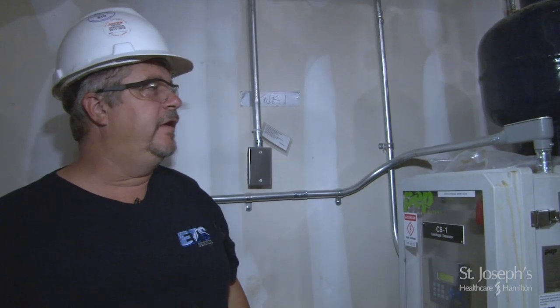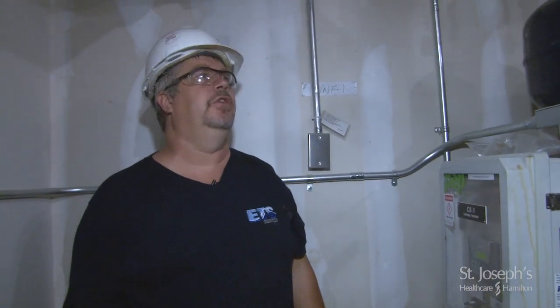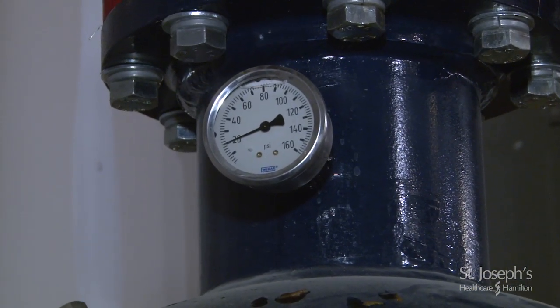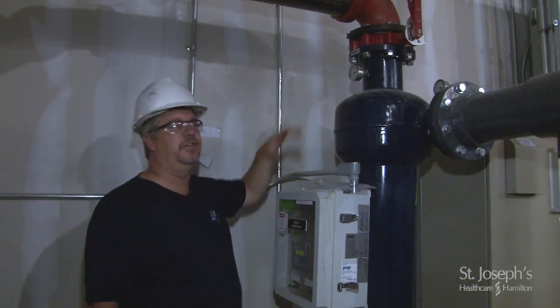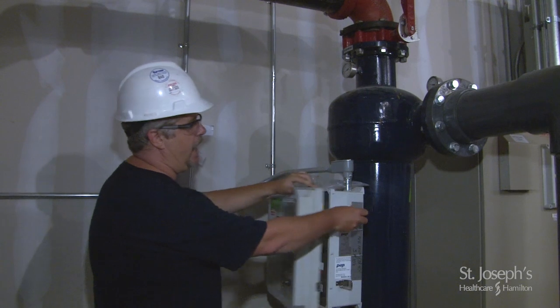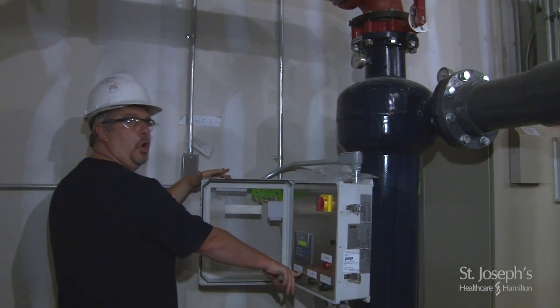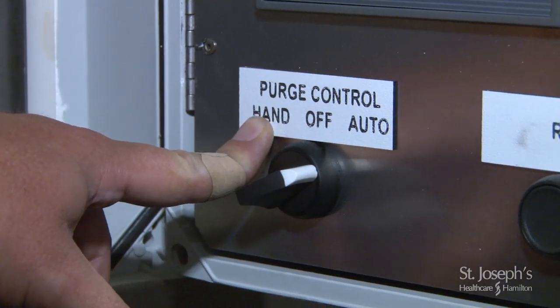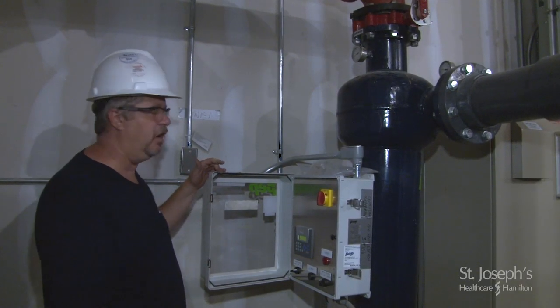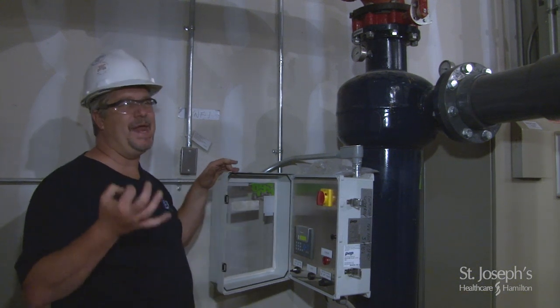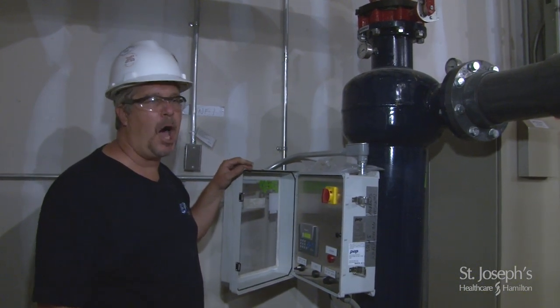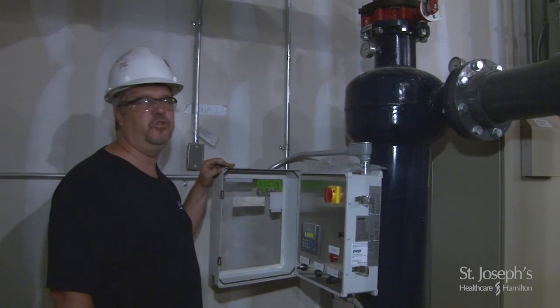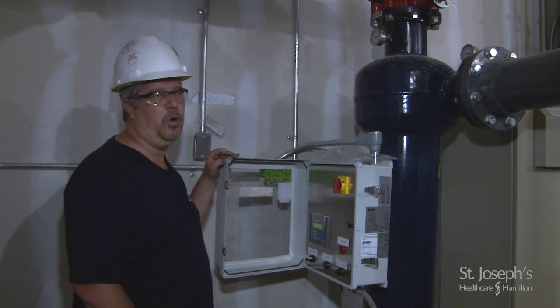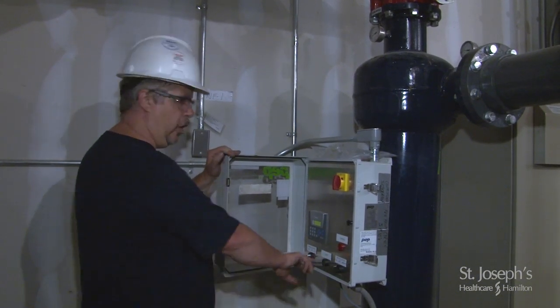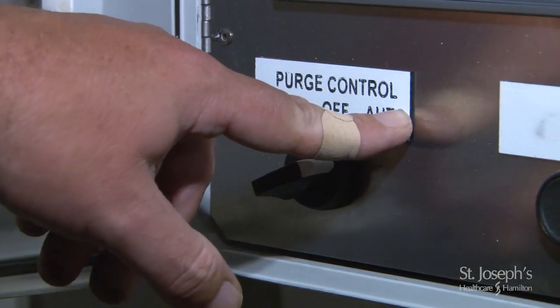Servicing of the unit, there really is not a lot to do with this unit. We can manually look at the pressure differential. If you feel it's getting high, but maybe the unit hasn't put itself into purge mode itself, you can switch that valve from the auto mode into hand mode. In other words, by putting it in hand mode, it will just start purging itself. Keeping in mind, in hand mode though, it will purge until you tell it to stop. There's no time on hand mode. It will just purge continuously till you take it off of hand mode. Always make sure if you're leaving the area that you've switched that back to auto mode.